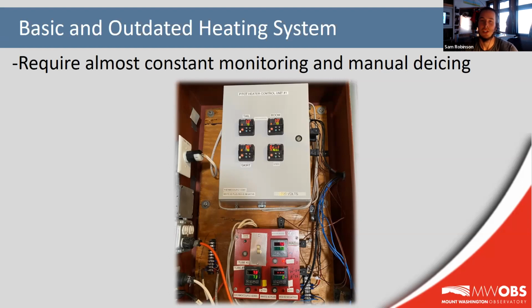And a less common issue that can and has occurred is moisture or ice making it into the pressure system itself. So due to that heating system not being able to keep up and evaporating it quickly enough, which then leads to a clog. A clog leads to a heavily dampened pressure, which then leads to erroneously low calculated wind speeds, as well as a loss of gust sensitivity. That means that the wind gusts or sudden changes in the wind speed just get smoothed out in the data, making the wind speed look almost steady.